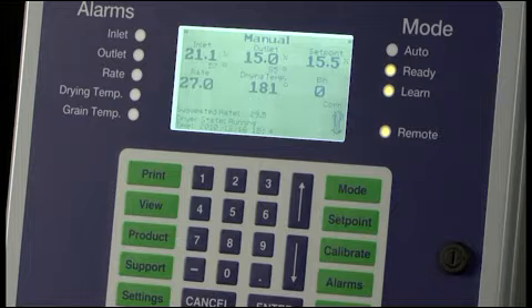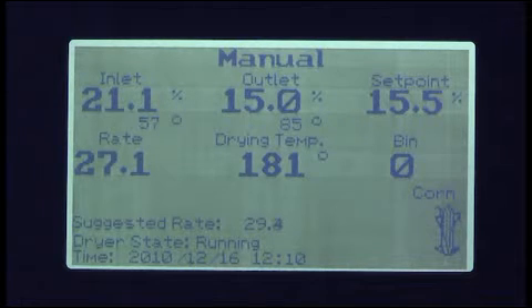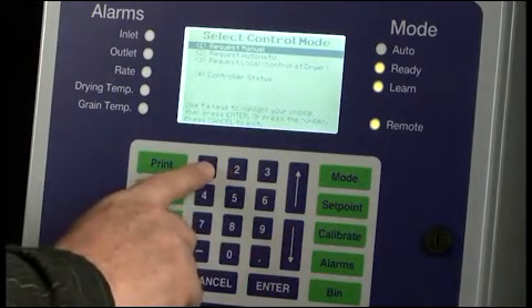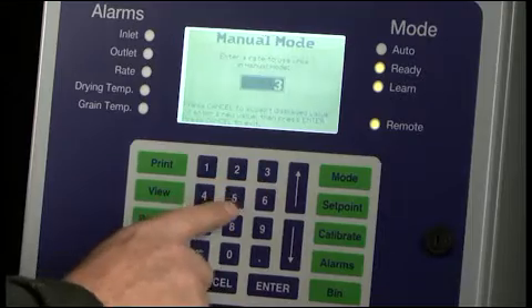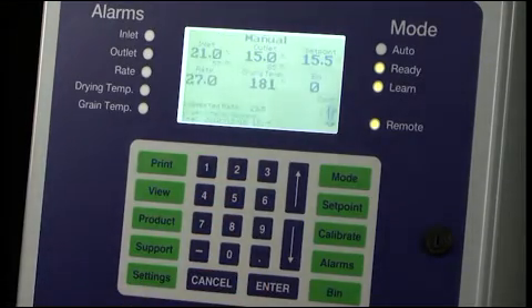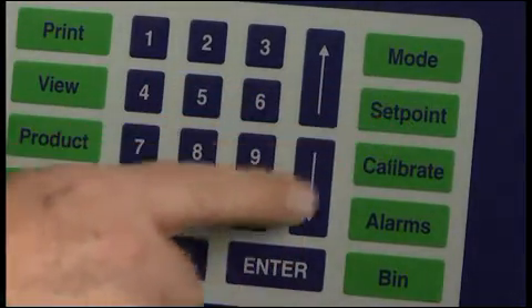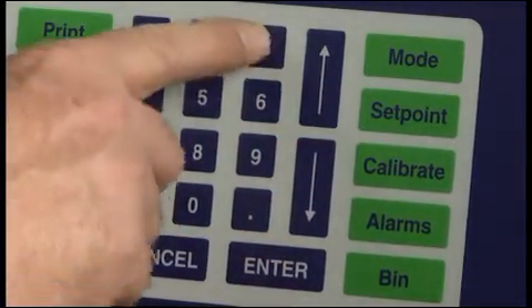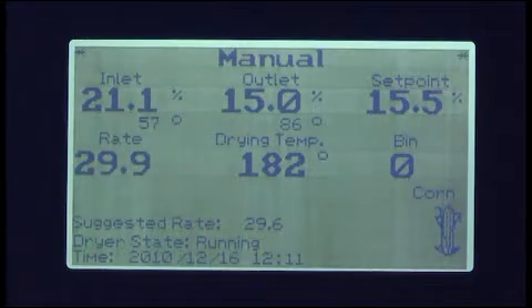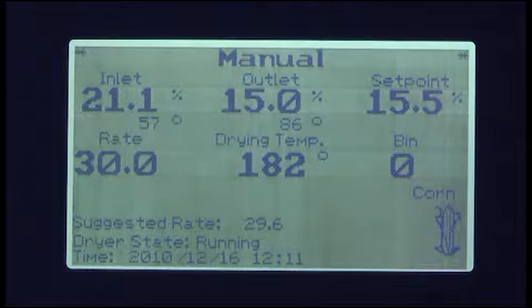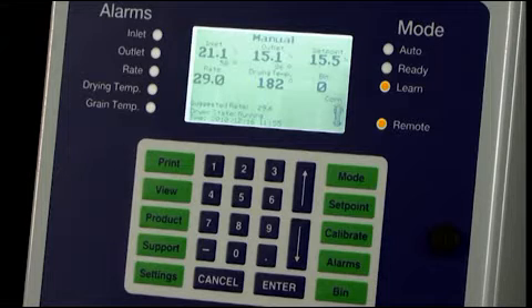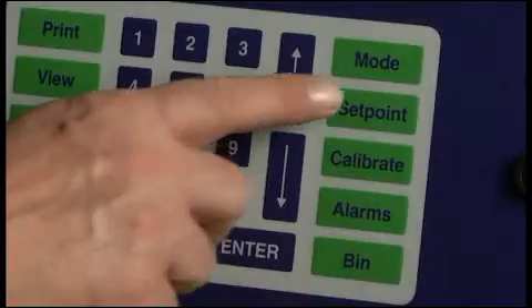Manual. In manual mode, the Dryer Master provides you with all the process information that it receives, but you are responsible for making changes to the dryer discharge rate. In manual mode, you can conveniently change the dryer discharge rate directly from the Dryer Master panel using the Set Point button, without having to go out to the dryer. Use the manual mode while you are drying very short runs, maybe only an hour or two, or while the Dryer Master is learning. Before the Dryer Master can go into auto mode, it must learn about your current drying conditions. While it is learning, the Learn status light will be on. When the Dryer Master is confident that its model of the drying process will provide good control, it turns on the Ready status light. Once the Ready light is on, you can switch to auto mode.